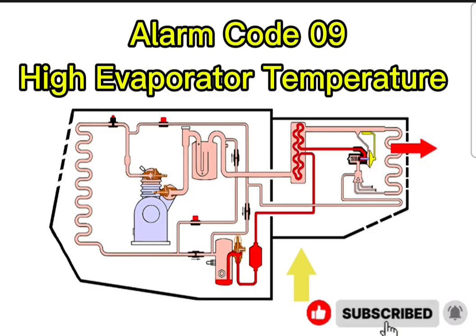Exactly. And the manual states this shutdown is triggered if the unit is running and hits one of two very specific thresholds. Okay, what are they? Either the evaporator coil temperature reaches greater than or equal to 155 degrees Fahrenheit, which, depending on where you're tuning in from, is a scorching 68 degrees Celsius. Wow, yeah. Or the discharge air temperature reaches greater than or equal to 135 degrees Fahrenheit or 57 Celsius. Those are the hard-coded limits of survival for this equipment.